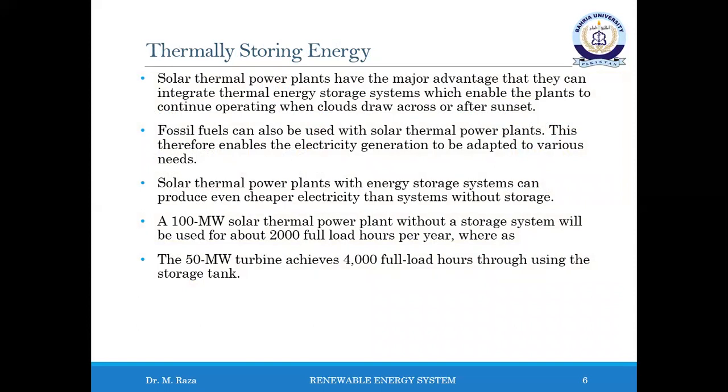This becomes evident when comparing, for example, a 100 megawatt solar thermal power plant without a storage system with a 50 megawatt system with the same sized solar field and the thermal storage tank at a good location. The 100 megawatt turbine will be used for about 2000 full load hours per year, whereas the 50 megawatt turbine achieves 4000 full load hours through using the storage tank. Both plants produce the same amount of electricity per year.